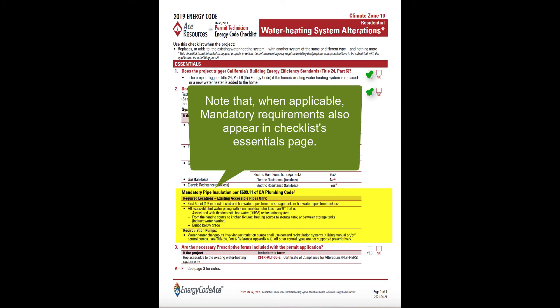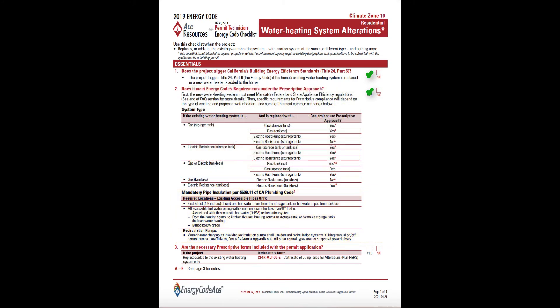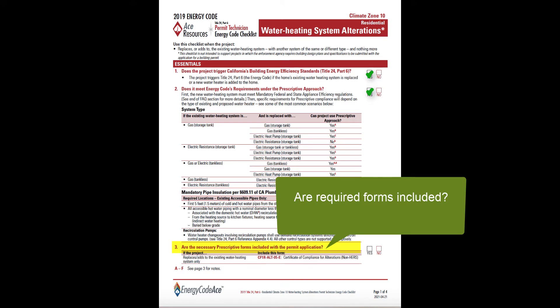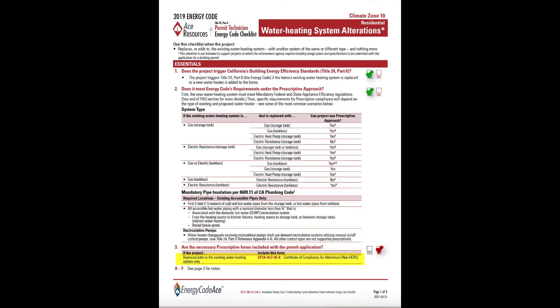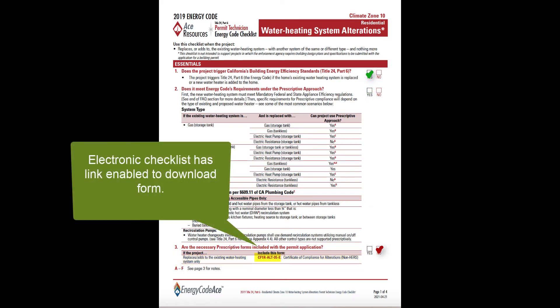Let's say the homeowner selected a compliant heat pump water heater and the project meets all mandatory and prescriptive requirements on the page 1 summary. The final question to ask in evaluating the permit application is whether all required energy compliance forms were submitted. Part 3 of the checklist page can help with this. Let's say the homeowner didn't submit any energy code forms — what's missing? In this case, replacement of a water heater requires submission of compliance form CF1R-Alt-05E.